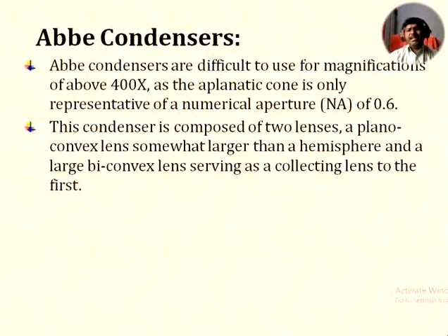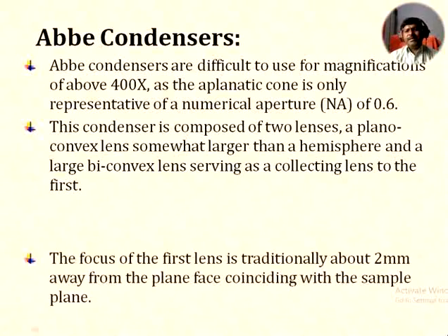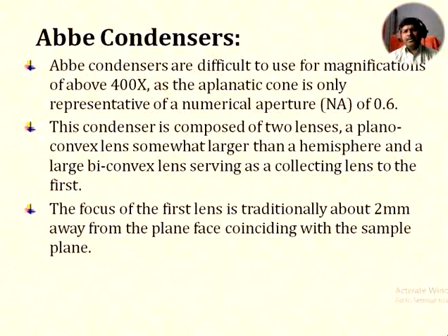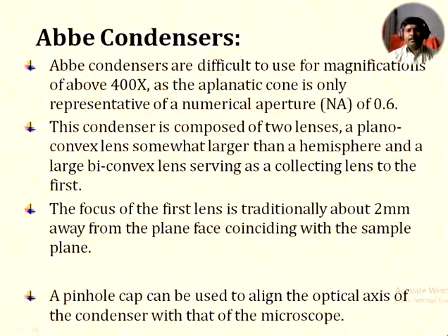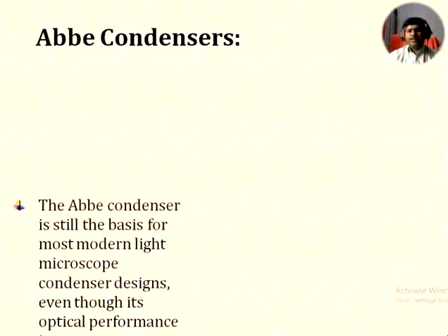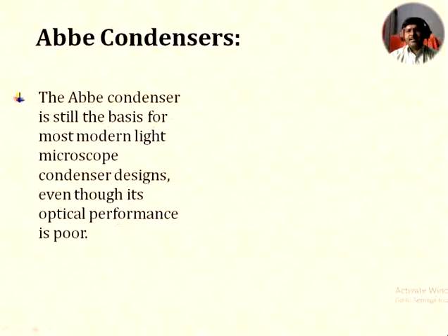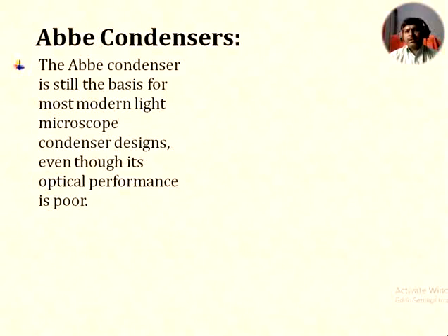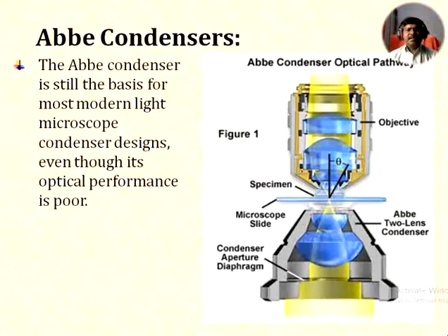The focus of the first lens is traditionally about 2 millimeters away from the plane face, coinciding with the sample plane. A pinhole cap can be used to align the optical axis of the condenser with that of the microscope.